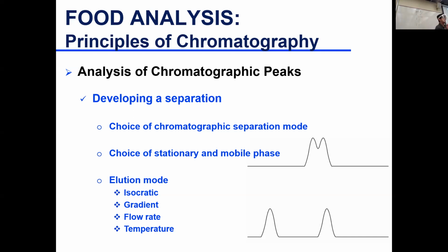That comes sooner, there's no time to equilibrate, there's no time to interact with the column. It's just the mobile phase is really going very fast. I lose separation. So flow rate is important. You have to find that sweet spot of flow rate to get the separation you want, but at the same time, no co-elution.